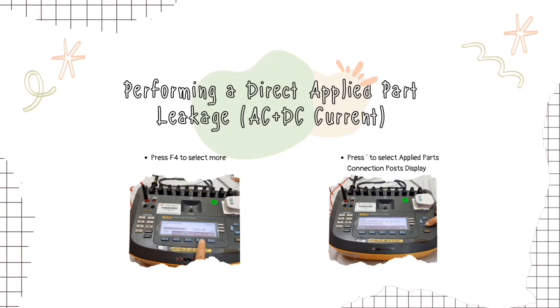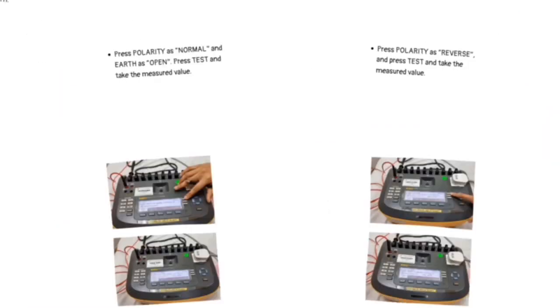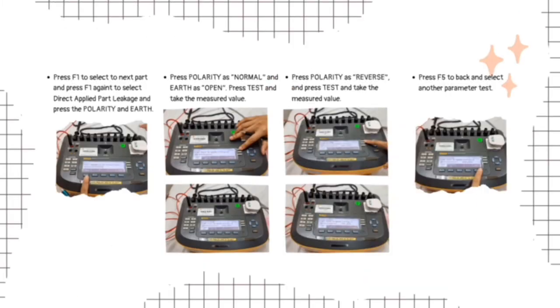Like before, we must press F4 to select more. Then we must choose the applied part connection post display. Then press F1 to select the next part and press F1 again to select direct applied part leakage and press the polarity and earth. Like before, we must choose the polarity either normal or reverse, and this time we must choose normal for the polarity and earth as open. Press test to take the result. Next is change the polarity to reverse and press test, and the measured value will be shown. Press F5 to go back and select another parameter test.